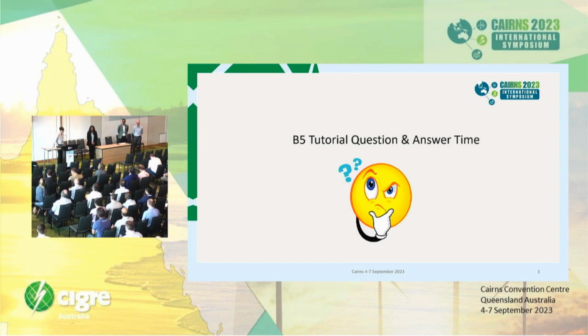Thank you. Thanks. It's a very good question, and it's something that we've actually had a lot of discussions with the NSPs over, whether to use metering or protection class CTs. What we landed on was that ideally we'd like metering class CTs if they're available. However, we would accept protection class CTs, given that most protection class CTs these days are comparable in accuracy to the associated metering class CTs. So we allow either, but preferably metering if they're available.